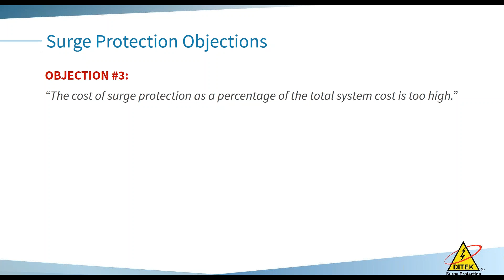Cost of surge protection as a percentage of the total system is sometimes seen as too high, but this is misleading. If you tried to make a system bulletproof, which is impossible due to direct lightning strikes, but if you called us out for a complete site survey covering everything from service entrance to low voltage protection, lighting controls, and battery backups, the whole package would be less than half the sales tax. It shouldn't price anybody out of a job.